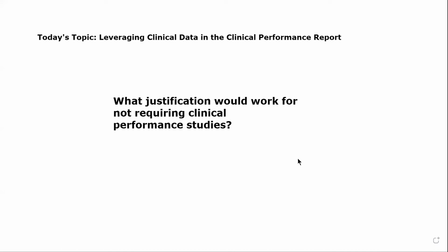What justification would work for not requiring clinical performance studies? I think ultimately it comes down to the classification of your IVD. There are some preliminary guidances suggesting that, for instance, in a Class A device, a clinical performance study would not be expected, especially for something like a reagent.